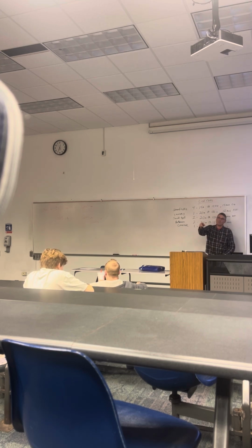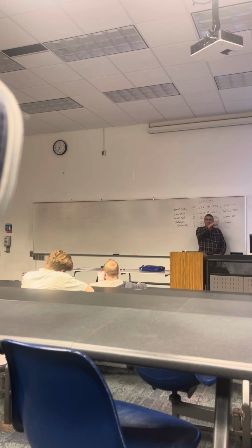So 3 times 120 is 360, times 2 is 720. You could put that where the bathroom fan was. If it doesn't give you the VA, you do amps times volts, that gives you the VA. Microwave, dishwasher, what else was out there? Freezer, refrigerator.